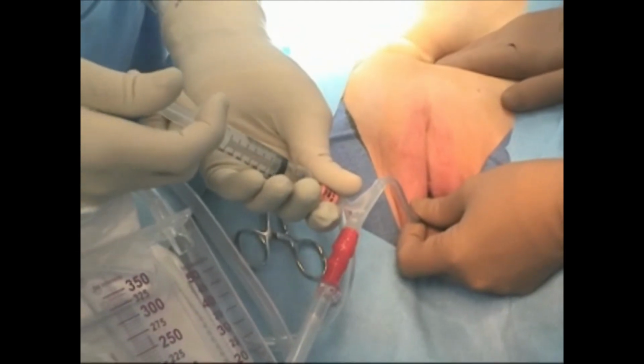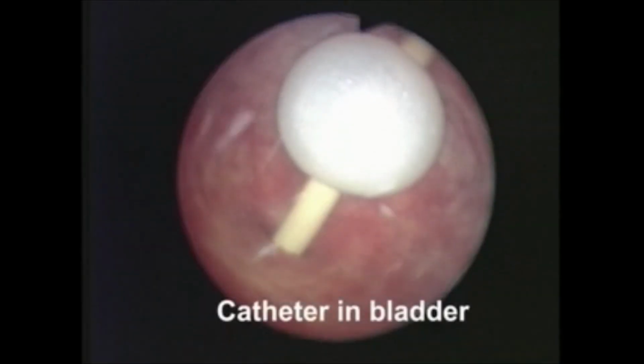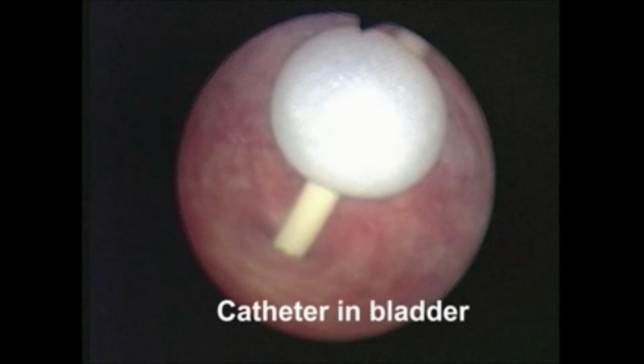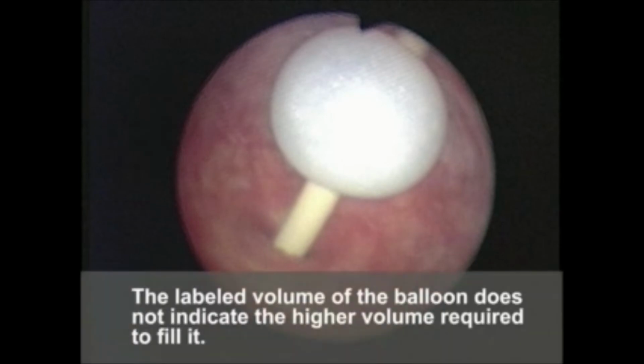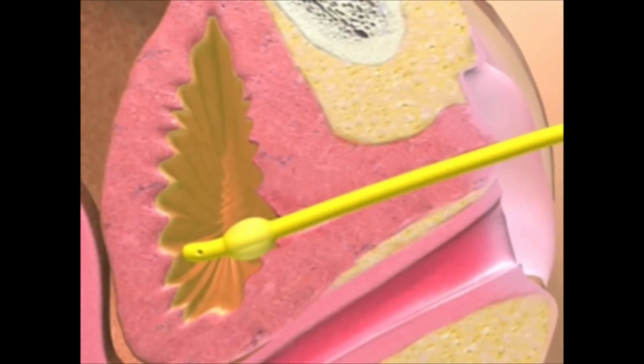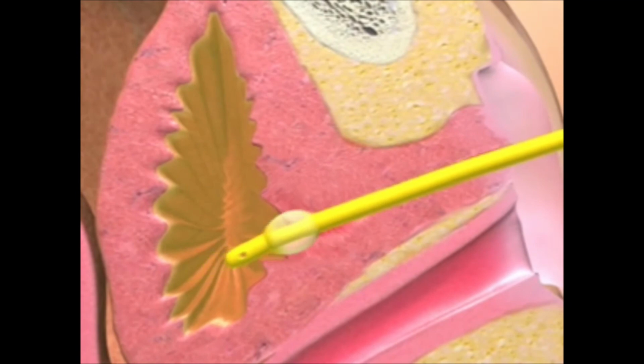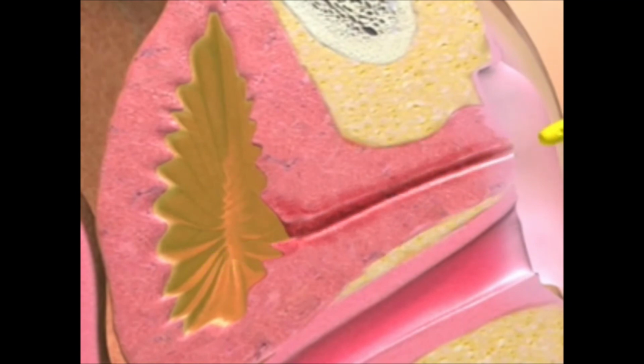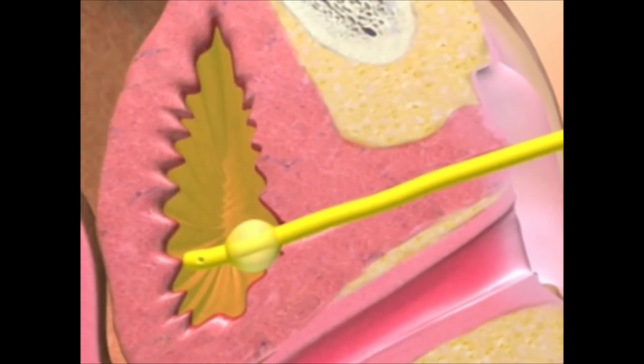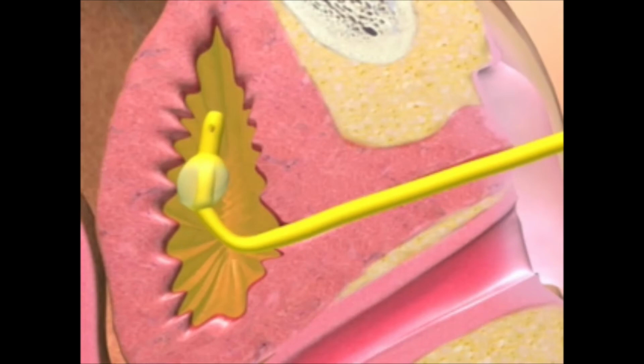Inject the entire 10 cc syringe of sterile water to inflate the 5 cc balloon completely. Note that the labeled volume of the balloon does not indicate the higher volume required to fill it properly. Partially filled balloons may lead to catheter displacement and urethral or bladder trauma. Saline should not be used because it may cause crystallization and valve malfunction. Air also should not be used because it allows the balloon to float in the bladder, possibly kinking the catheter.